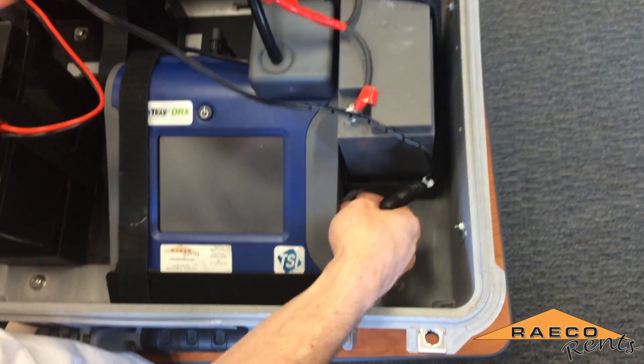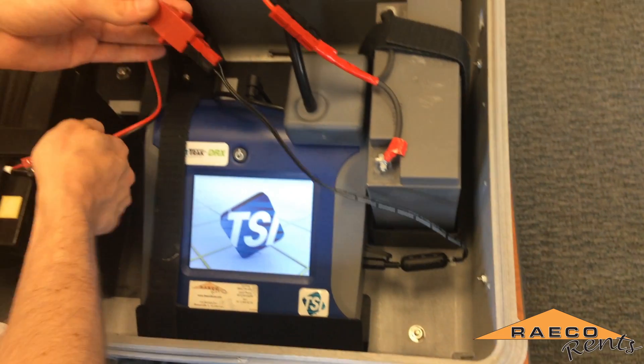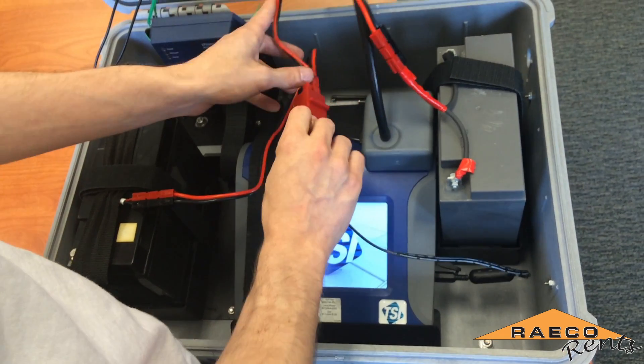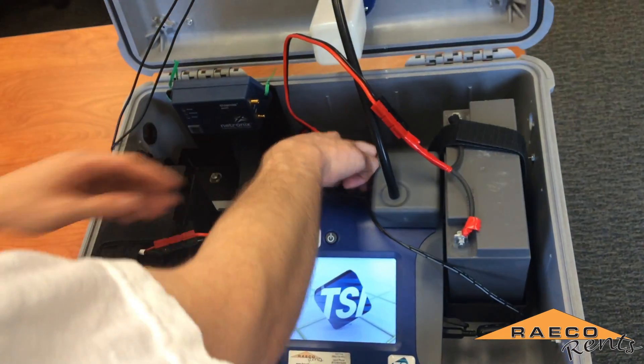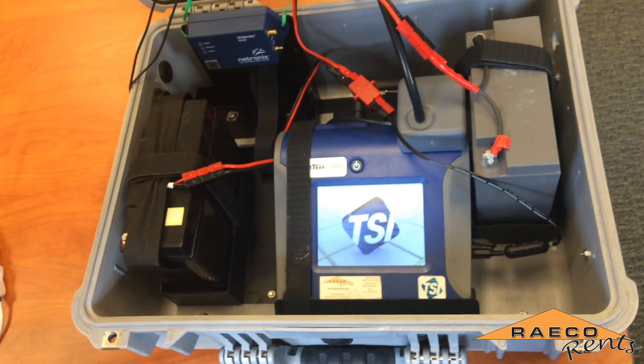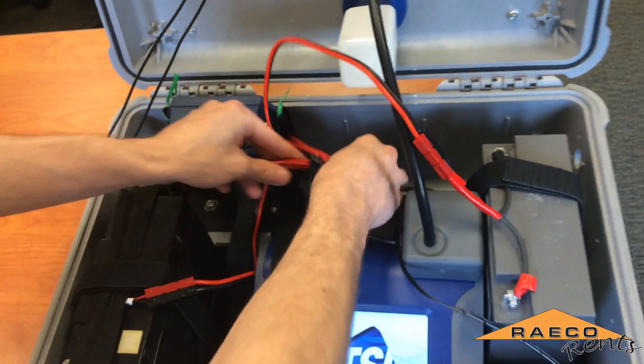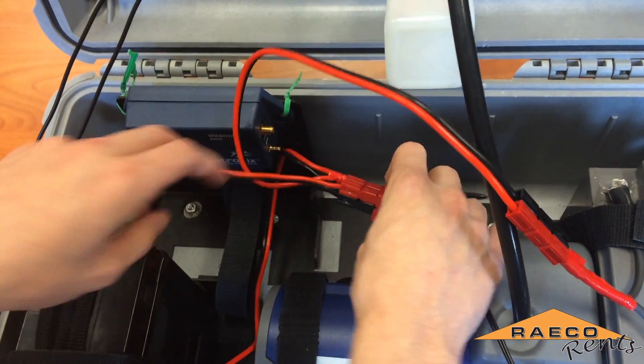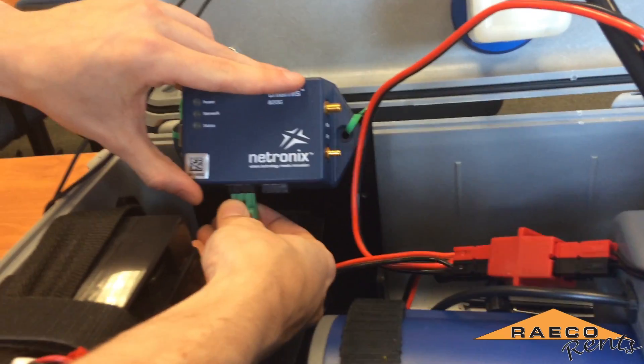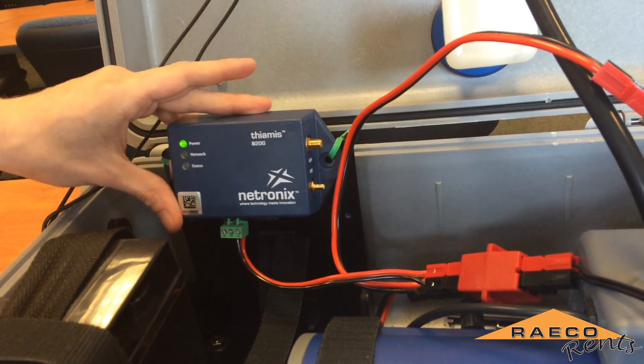We'll plug in the dust track, which should turn it on right away. If the dust track for some reason didn't turn on, you would want to check the cables to make sure there's no breaks, and just make sure that the batteries are charged. The last power connection we'll make is to the Thiamis device, which is a remote monitoring data collection unit. The power port for that is right on the bottom — that just plugs in and you should see the power indicator turn on.